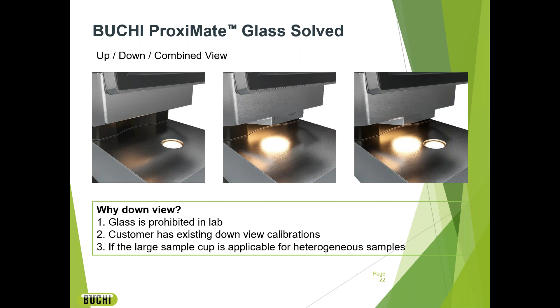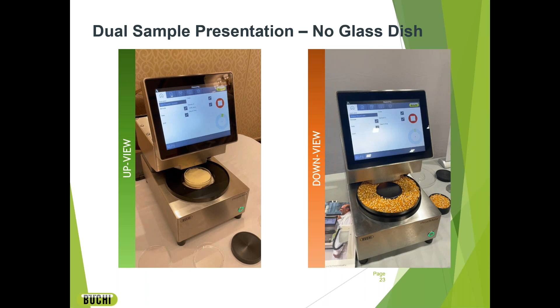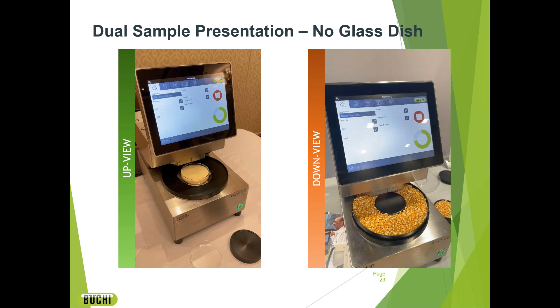Why is this important? Plastics have their own NIR spectra, which can influence the measurement output, leading to perceived shifts in your results. Moreover, down view also allows the use of large volume sample dishes, which are particularly useful with inhomogeneous samples, for example, corn, allowing the measurements to be averaged over a much larger sample area. This is a quick demonstration of the ProxiMate up view, where light is directed to the sample through a glass petri dish, and the down view mode with a large sample dish where NIR light is directed to the sample itself without any packaging. In both cases, the collection of NIR spectra is as simple as loading the sample, positioning it appropriately, and hitting the measurement button.